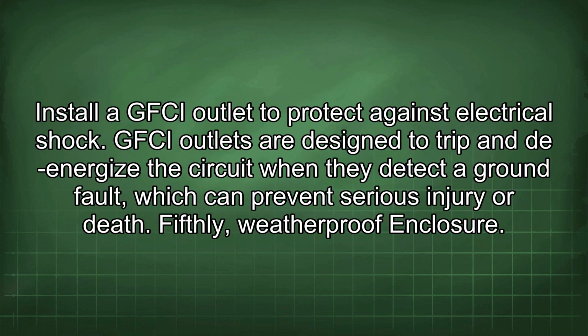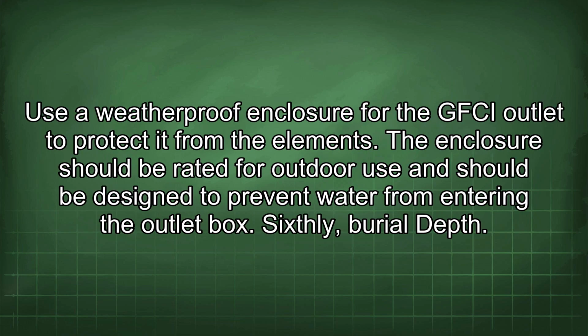Install a GFCI outlet to protect against electrical shock. GFCI outlets are designed to trip and de-energize the circuit when they detect a ground fault, which can prevent serious injury or death. Fifthly, weatherproof enclosure. Use a weatherproof enclosure for the GFCI outlet to protect it from the elements. The enclosure should be rated for outdoor use and should be designed to prevent water from entering the outlet box.